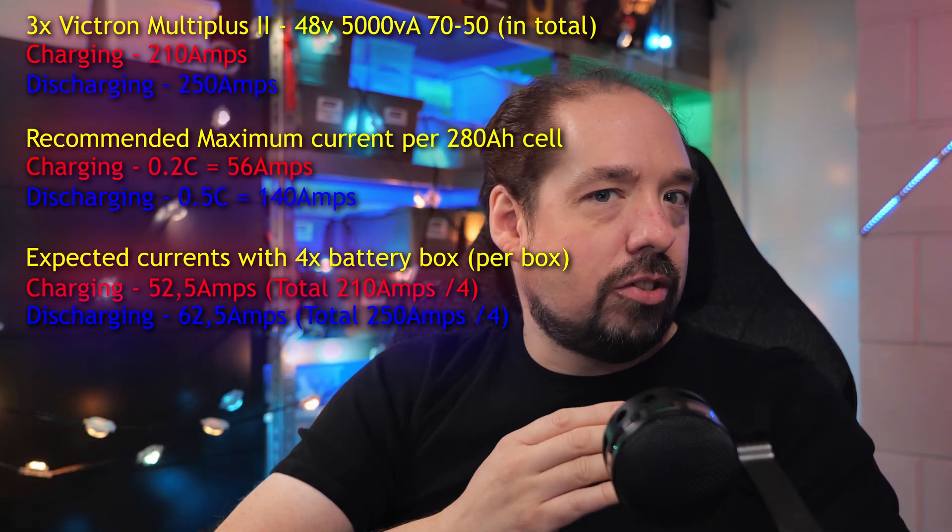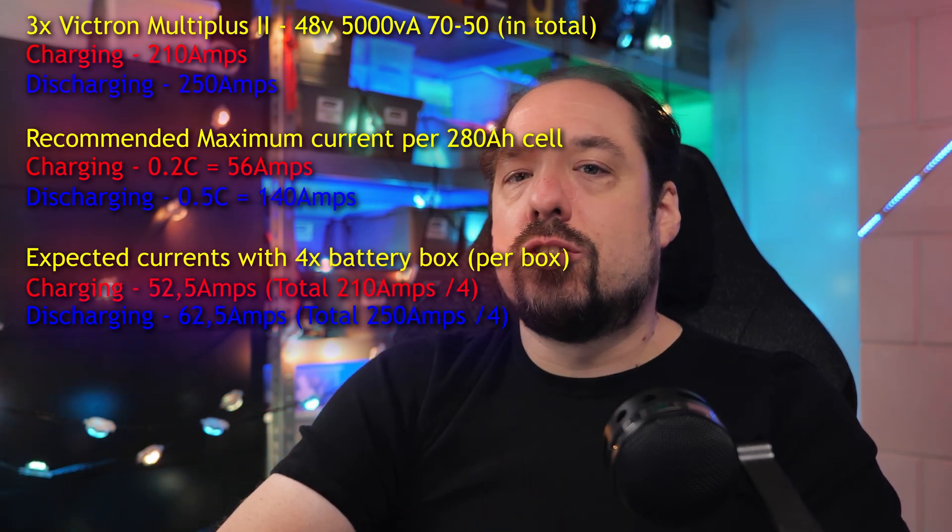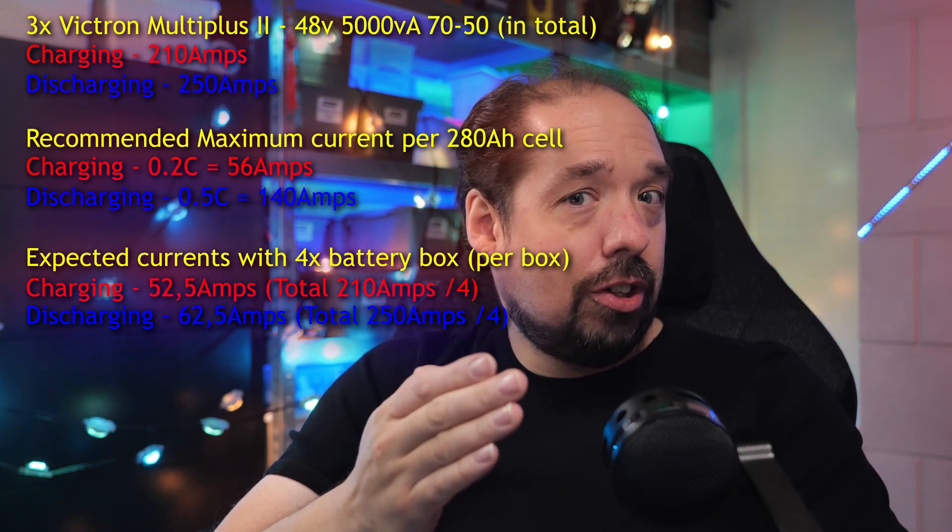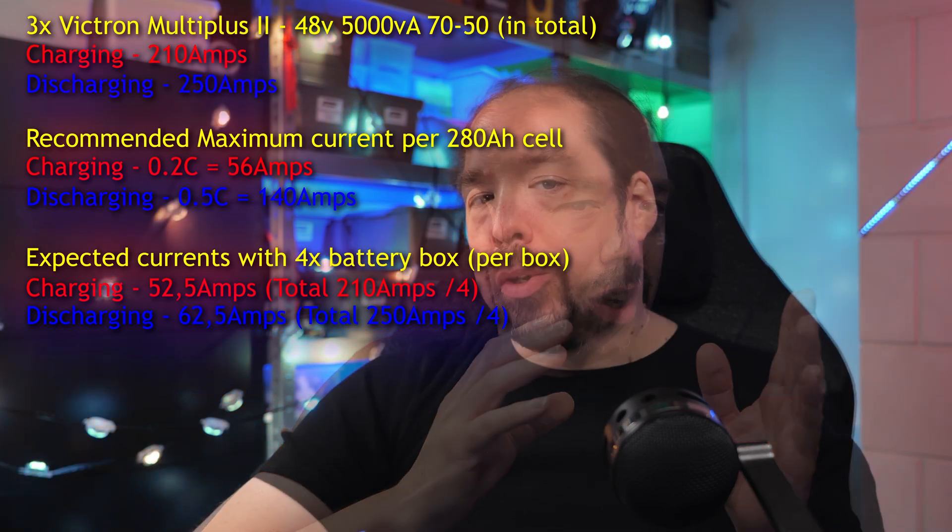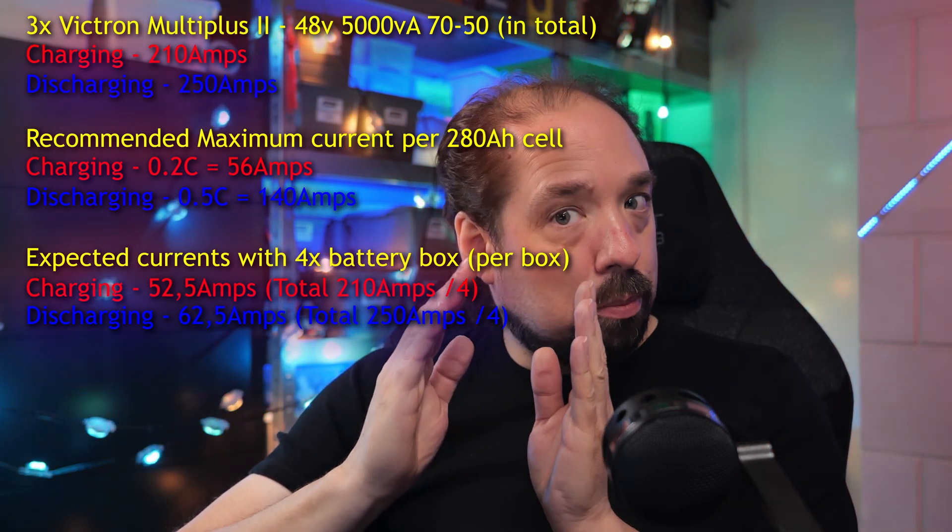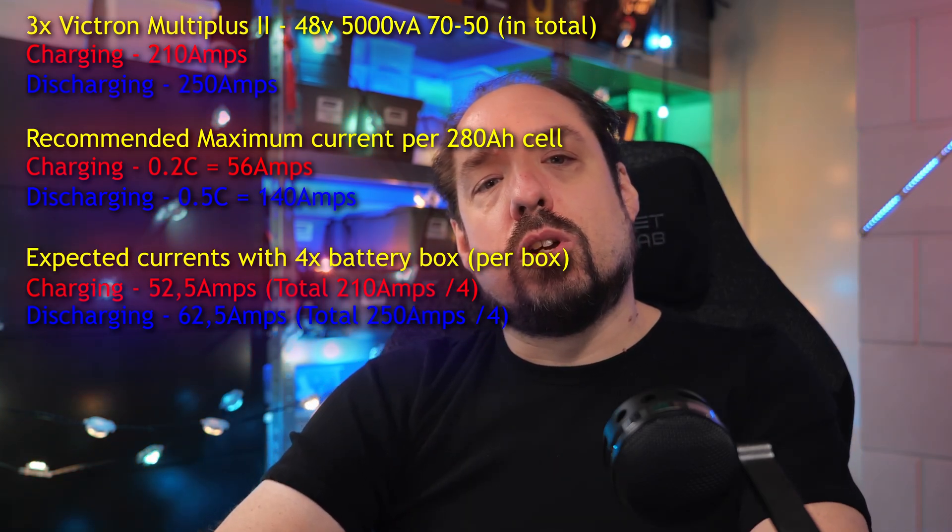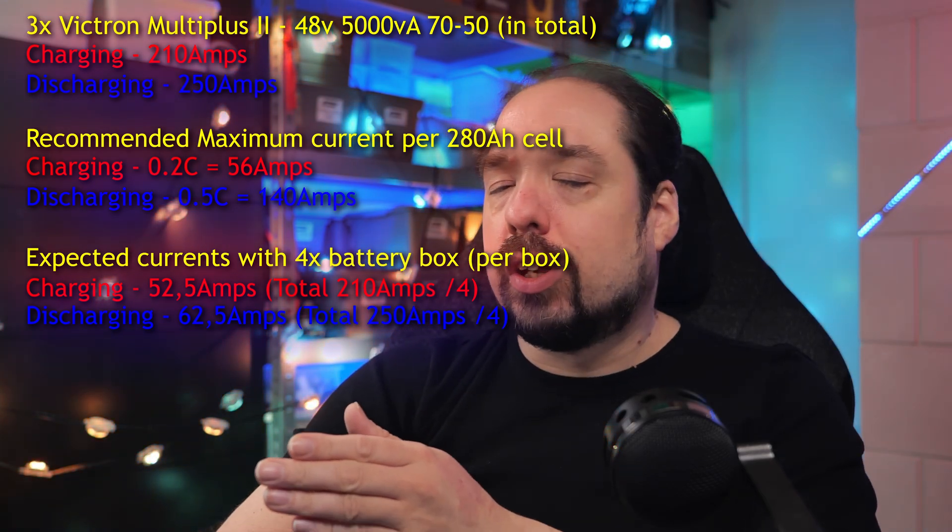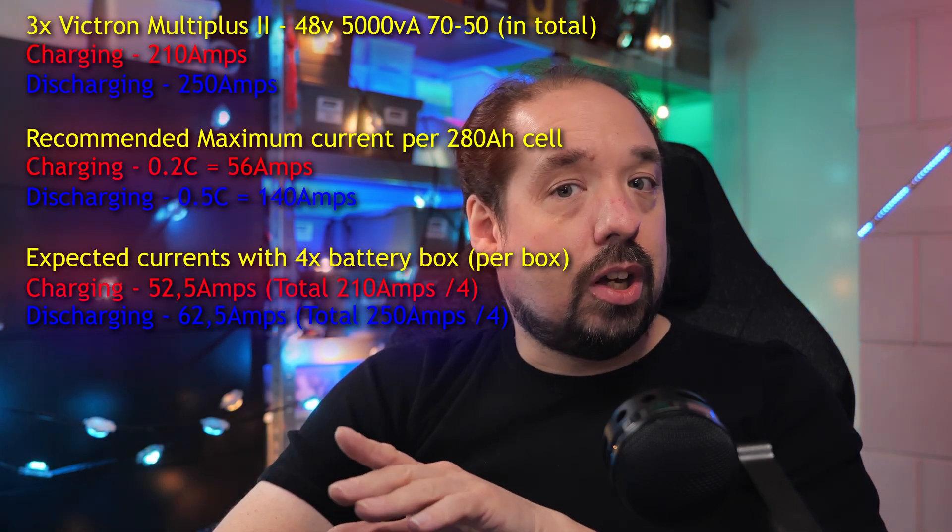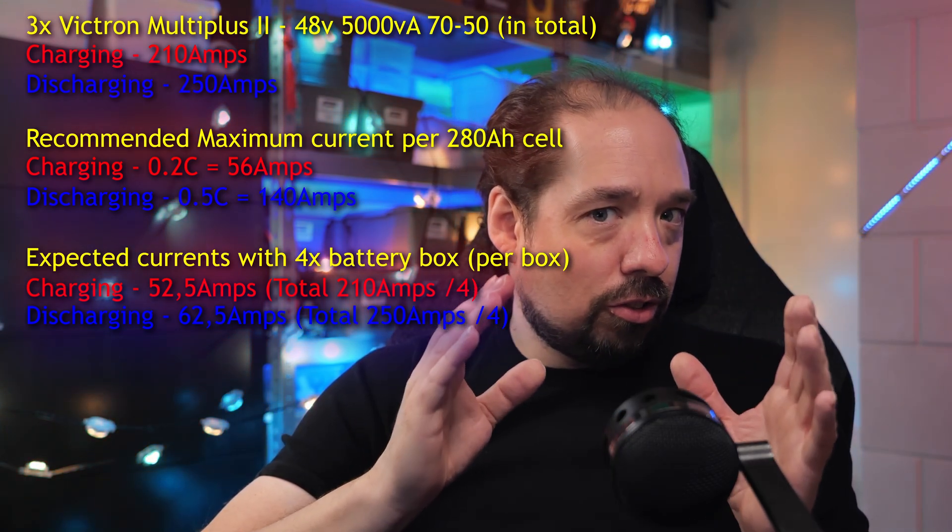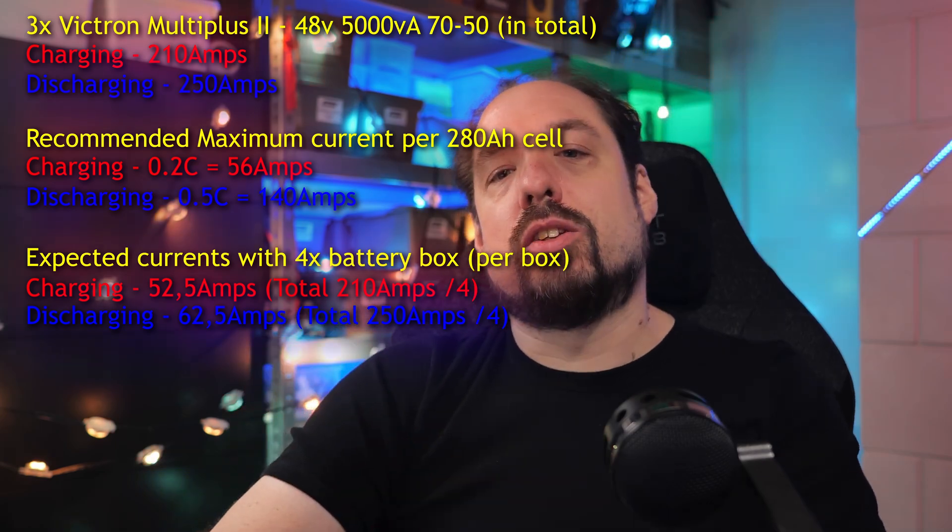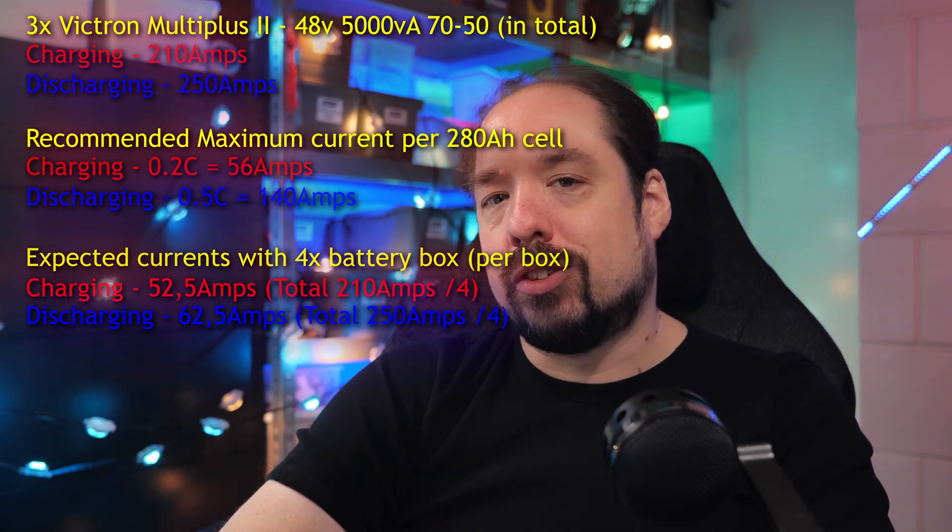The reasoning behind that is that although we are going to have 16 cells in a single battery box, because we're putting those 16 cells in series, this figure doesn't change because of that. But because we're going to be putting four battery boxes in parallel, it does share all the load between all of them that way, and brings everything together as a well-matched system. This also means our cables to the batteries, and everything in between needs to be sized for this total current and the individual expected current per battery box.